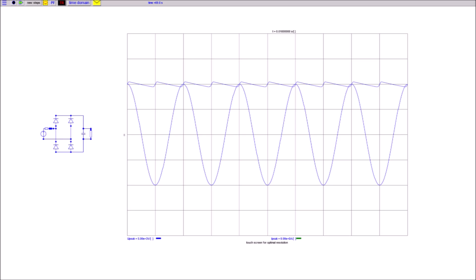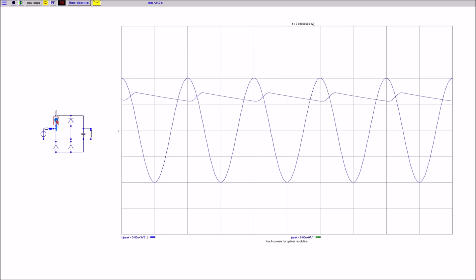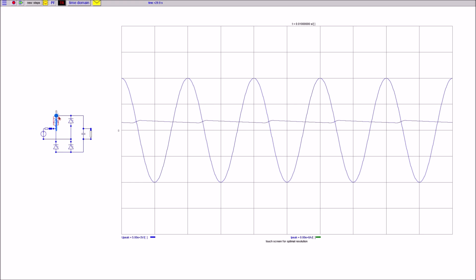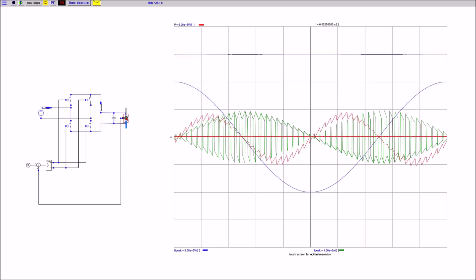The diode rectifier DC output voltage is typically equal to or less than the peak of the AC side voltage. A thyristor rectifier enables controlling the DC voltage by varying the firing angle of the thyristor in reference to the AC voltage. The later in the half cycle of the AC voltage the thyristor is fired, the lower the DC voltage will be.